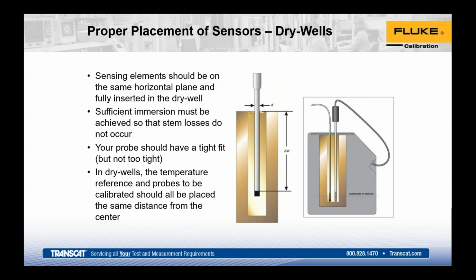I didn't include a third picture here, but this would also be appropriate if, say, you had a shorter probe and you could immerse, say, your reference, not all the way to the bottom, but say up 2 inches, and then say your device you're testing doesn't quite meet the bottom, it's 2 inches short, you could align them that way. And that would also be an appropriate way of helping to reduce the uniformity or gradient errors that you do run up against in some of the heat sources.